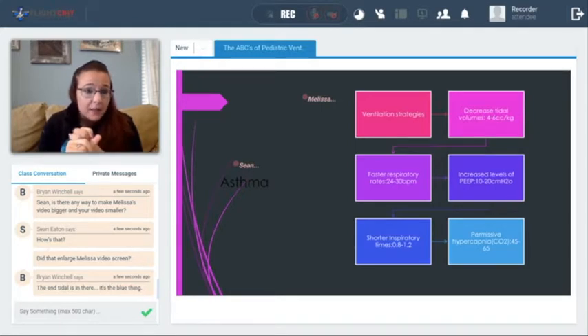So think about that when you decide that you're going to bail from volume ventilation and go to pressure control ventilation, because here's where I see people fail. Think about how you had your high pressure alarm set at 40, and your vent was not able to deliver the tidal volume wanted at 40. So when you switch into a pressure control mode, think of that as your inspiratory pressure or pressure control setting. On my vent, it's not PEEP compensated. So if I am deciding that I'm going to try and push in 40 centimeters of water pressure into this kiddo to see what kind of tidal volume I can get, and then I'm going to use a PEEP of 5, on my vent I have to dial in 35 for my pressure control and then a PEEP of 5.